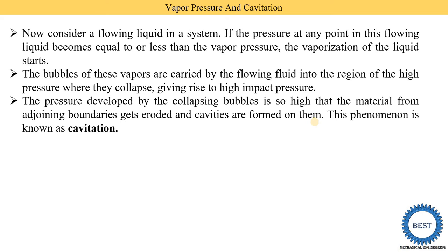This phenomena is known as cavitation. When these bubbles collapse near metallic pipe material at the boundaries, some material is eroded from the pipe and small cavities are created in the pipe. Due to these collapsing vapor bubbles, small cavities are formed — hence it is called cavitation.